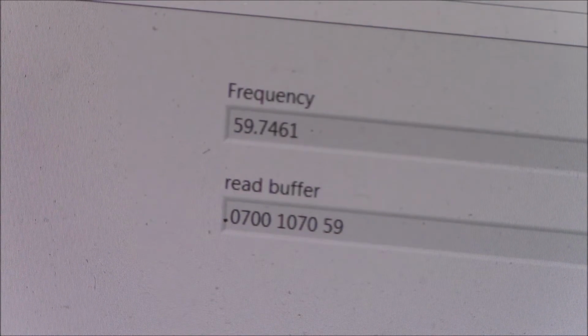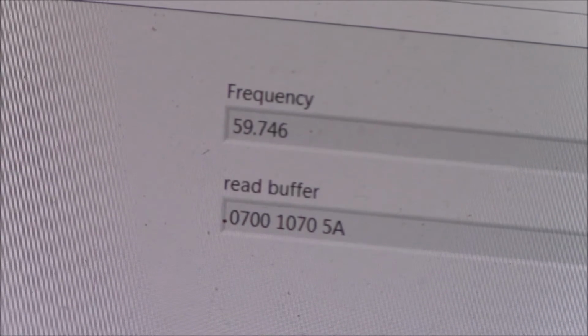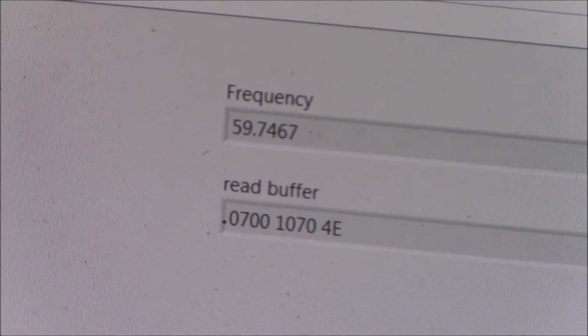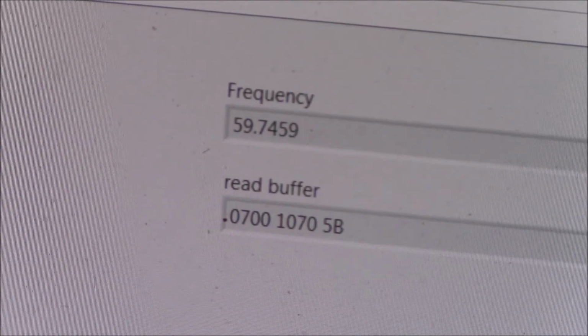Here we are displaying the frequency we're reading back, and as we're using the synthesizer, I can change the frequency up, to 67 hertz, maybe much higher, perhaps 80 hertz. Back down to around 60 hertz. The delay is due to our linear regression used to acquire more accurate frequency information. This frequency is not coming from the line, instead it is coming from our power synthesizer, so it is being driven by a function generator currently.